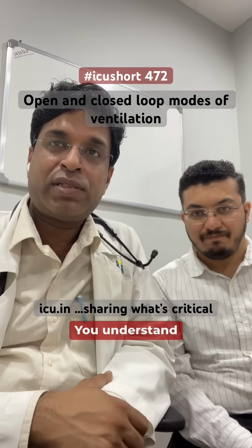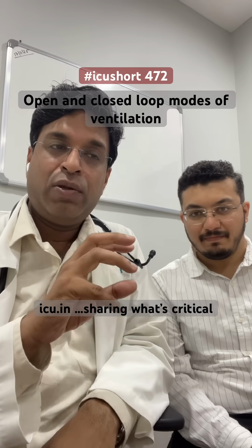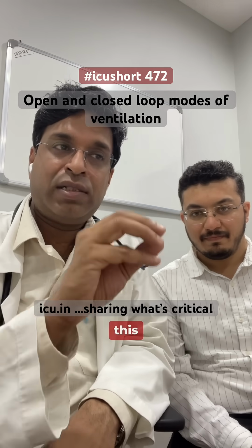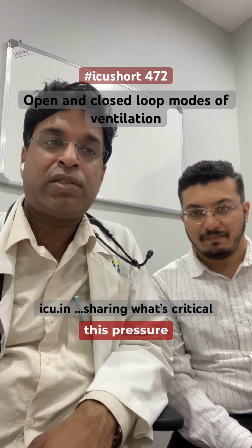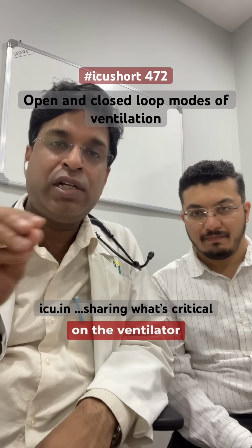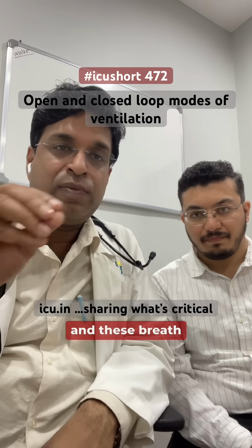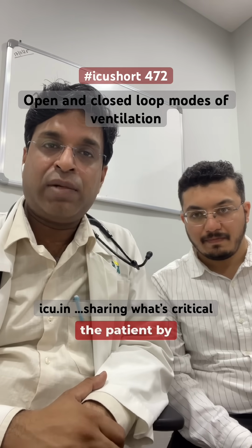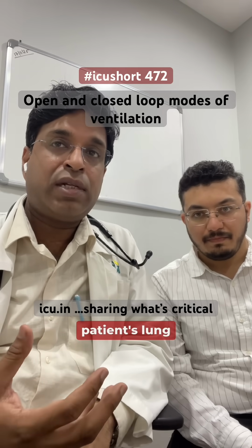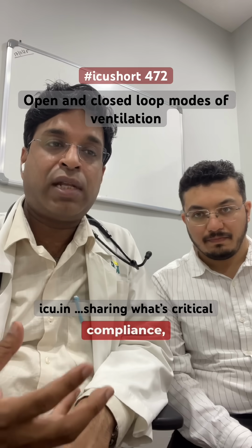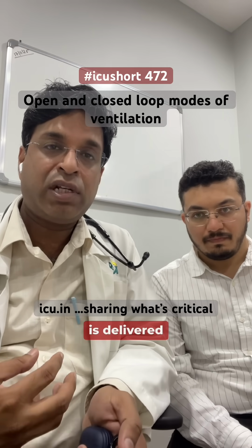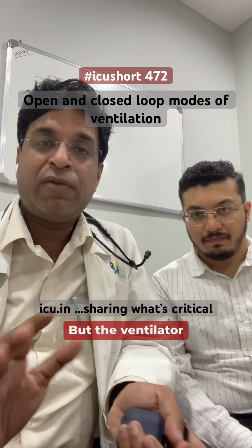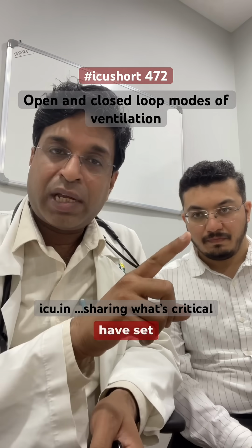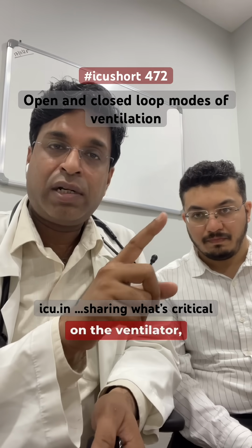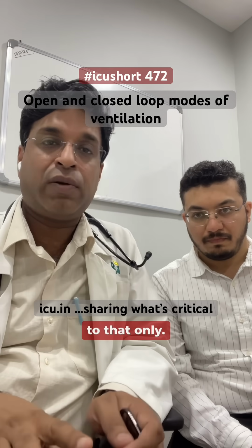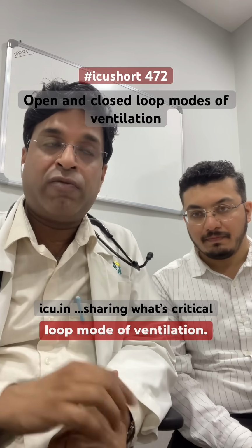So it's very simple. In open loop, you decide certain settings on the ventilator, this tidal volume, this pressure support or whatever, and it needs to be delivered to the patient. And this breath is delivered to the patient by the ventilator. But based on the patient's lung mechanics, resistance, compliance, elastance, it may happen that the actual breath delivered has certain variations. But the ventilator doesn't care about it. Whatever you have decided on the ventilator, the next breath will come according to that only. So this is an open loop mode of ventilation.